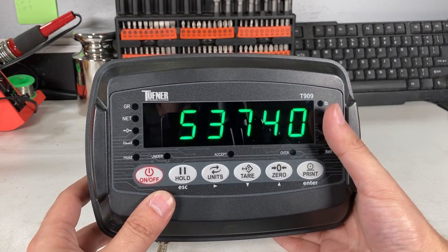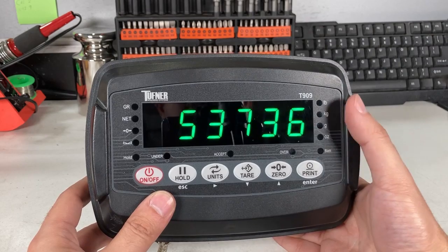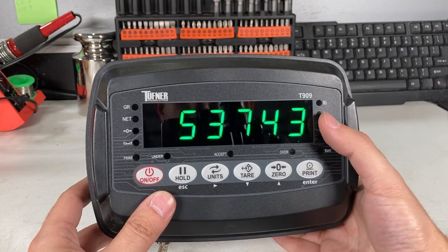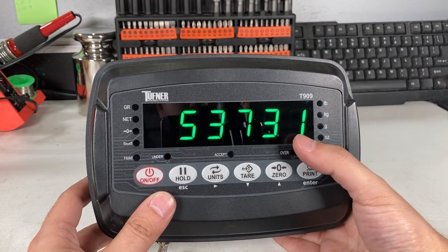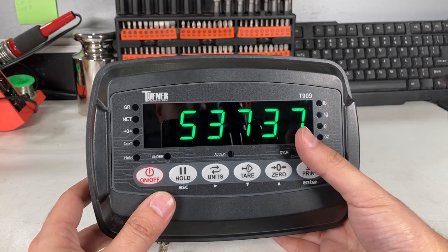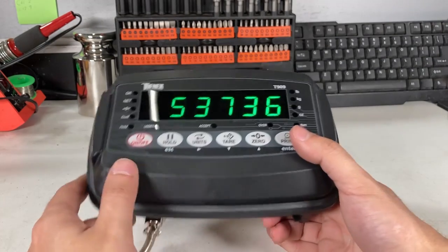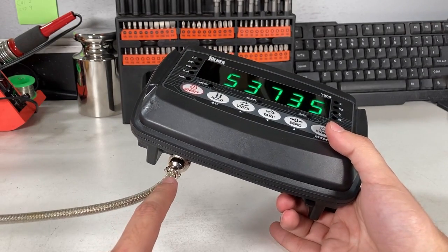The indicator calibration is what actually tells it these numbers are this much weight. So if you put weight on it, it should go up. You remove weight, it should go down. If this is correct, then the rest of the calibration is fine. If not, recheck if this cable is damaged.